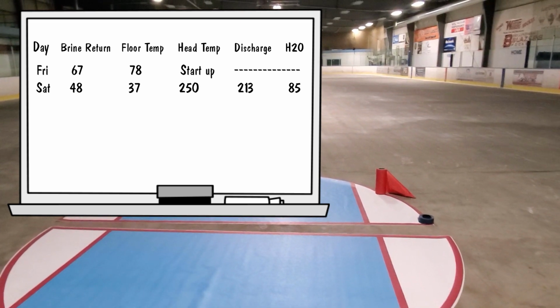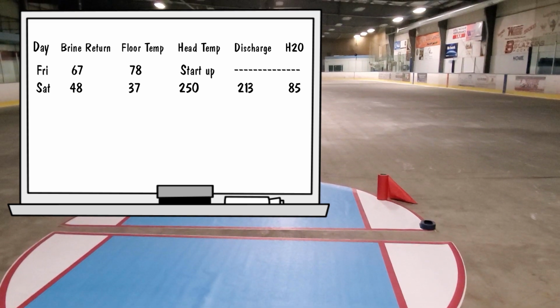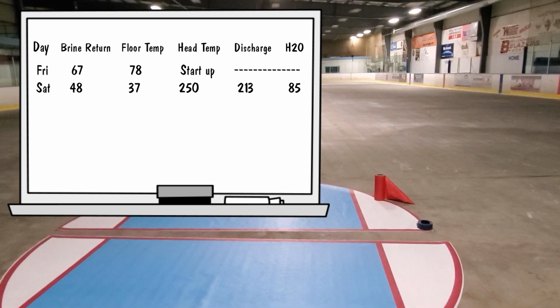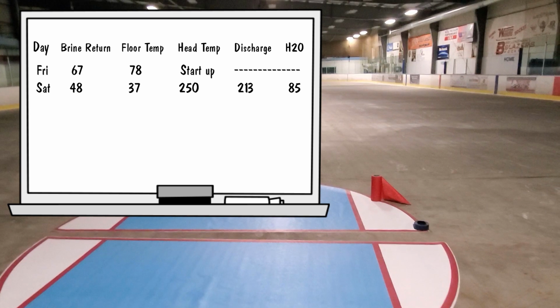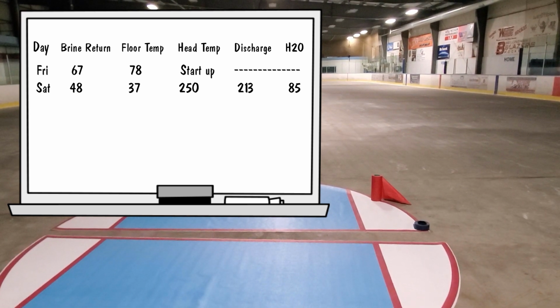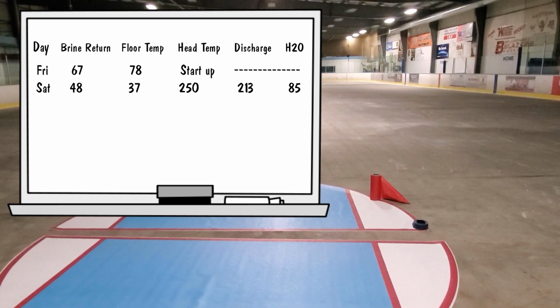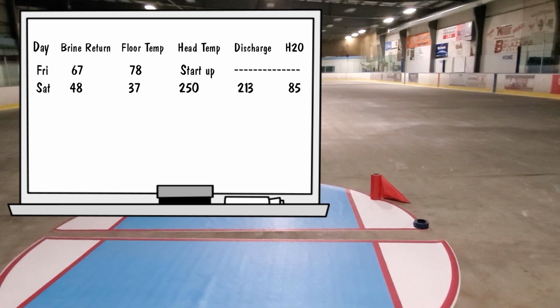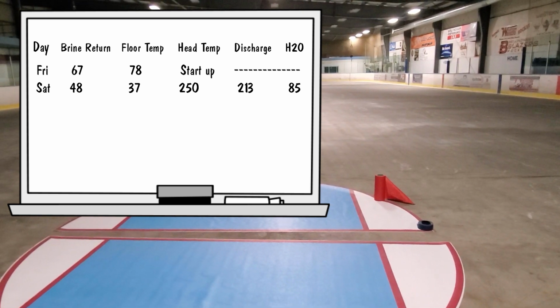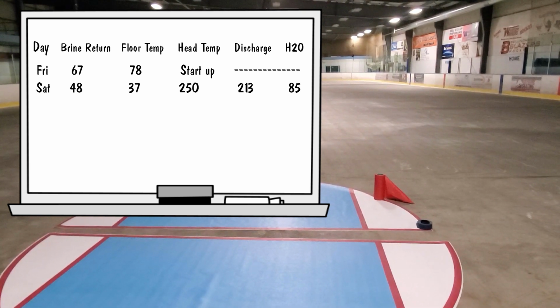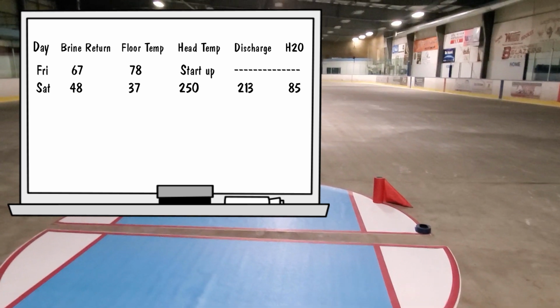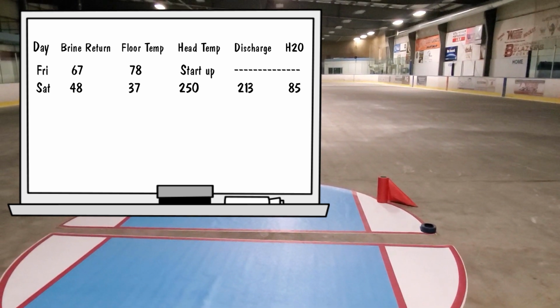Our discharge temperature was at 213, and suction's at 48, which is on the high end, but you expect that because the whole system is still trying to cool down. I didn't really want to try to explain that. And the condenser water temp, the water outside, was at 85 degrees. So let's talk about that head temperature, the 250 degree number, because that was really, really hot.